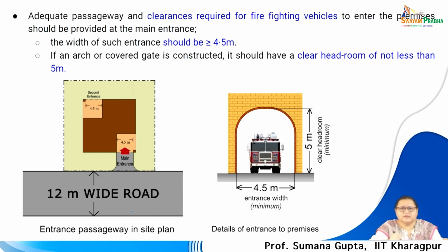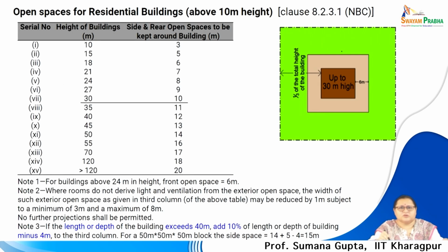Also, coming to the site requirement for the entry of the fire tender, you see a minimum of 4.5 meters width is required. You can see this dimension, it is 4.5 meters. Also, the height you see for the gate. This may be the entrance gate, and it should be 5 meter high and 4.5 meter clear. Only then can a fire tender move into it, and that has to be maintained for the site.